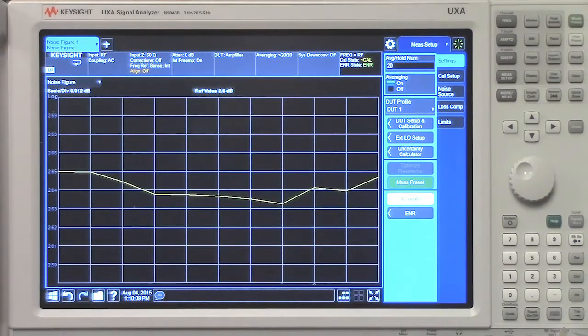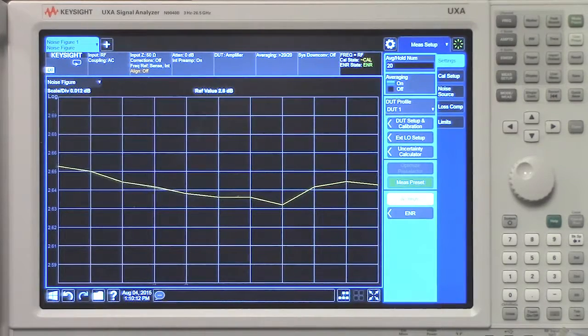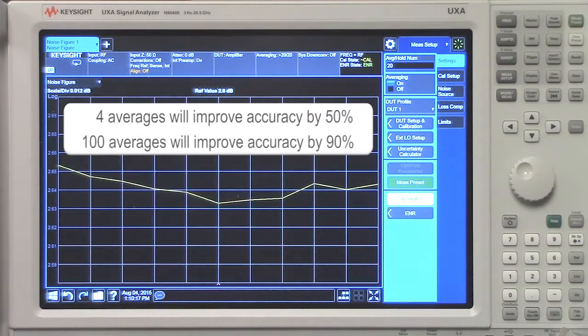Jitter uncertainties are reduced by the square root of n, where n is the number of averages. Four averages will improve accuracy by 50%, while 100 averages will improve the accuracy by 90%.